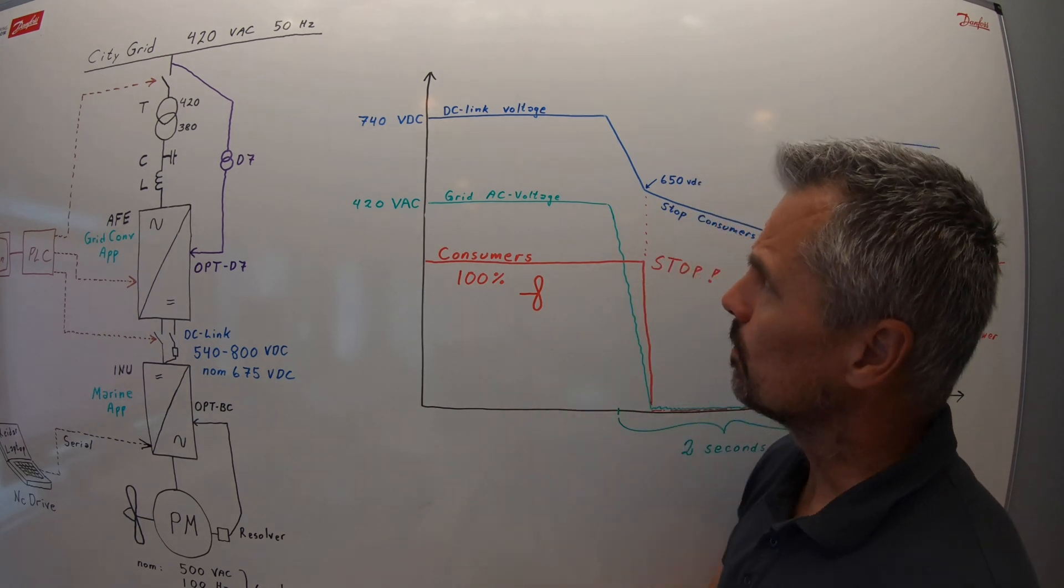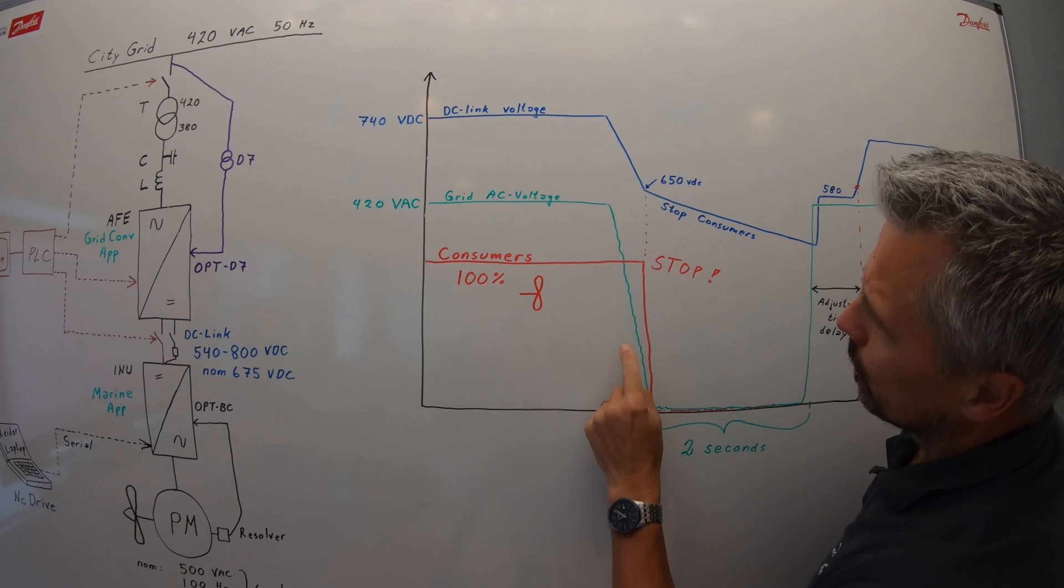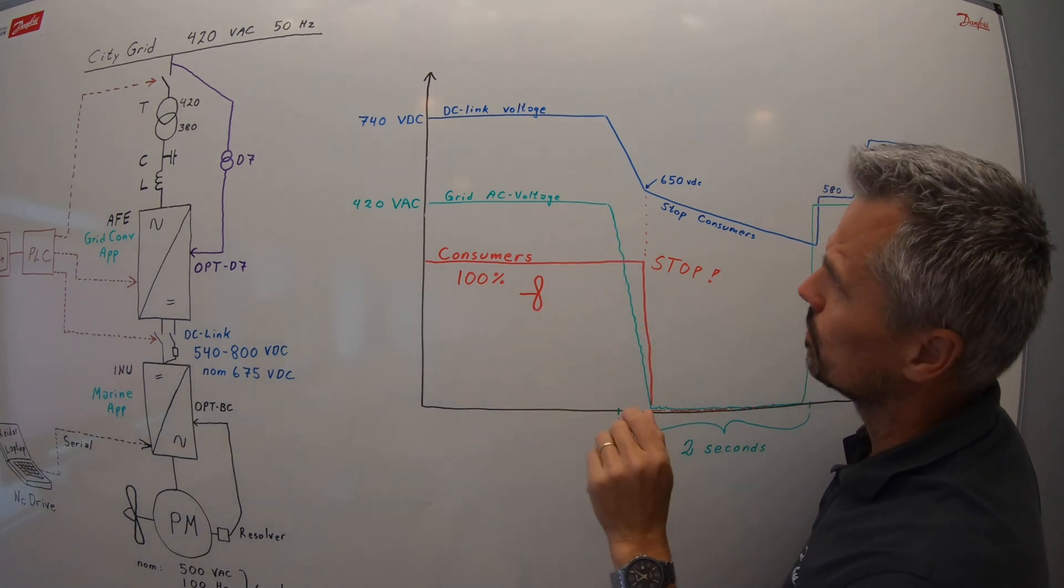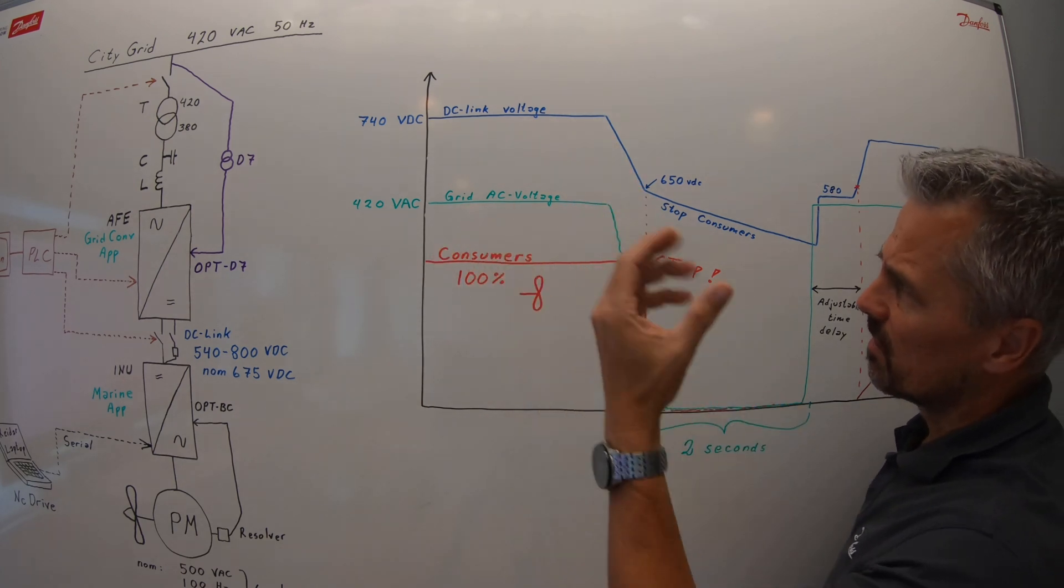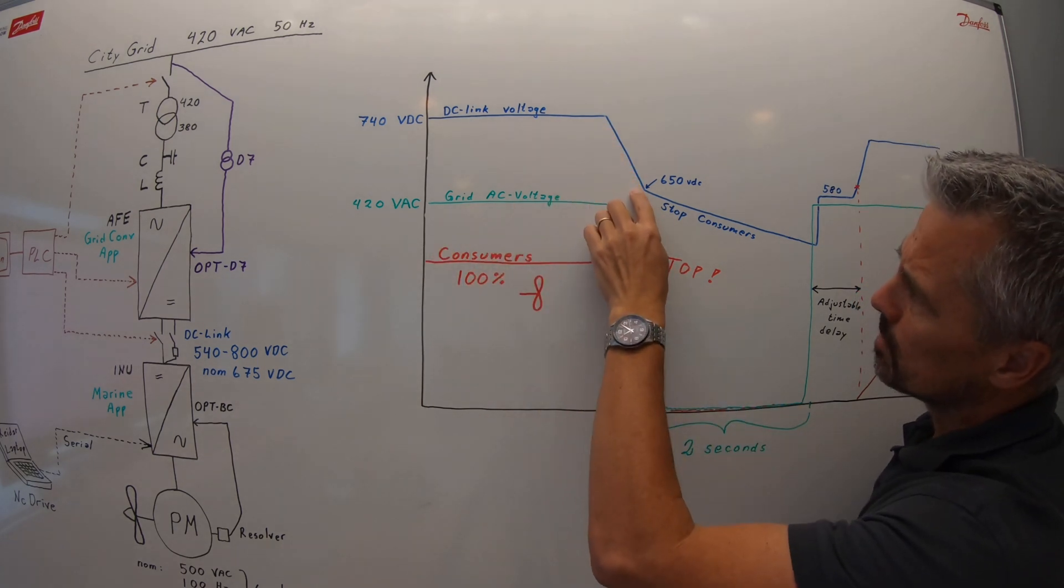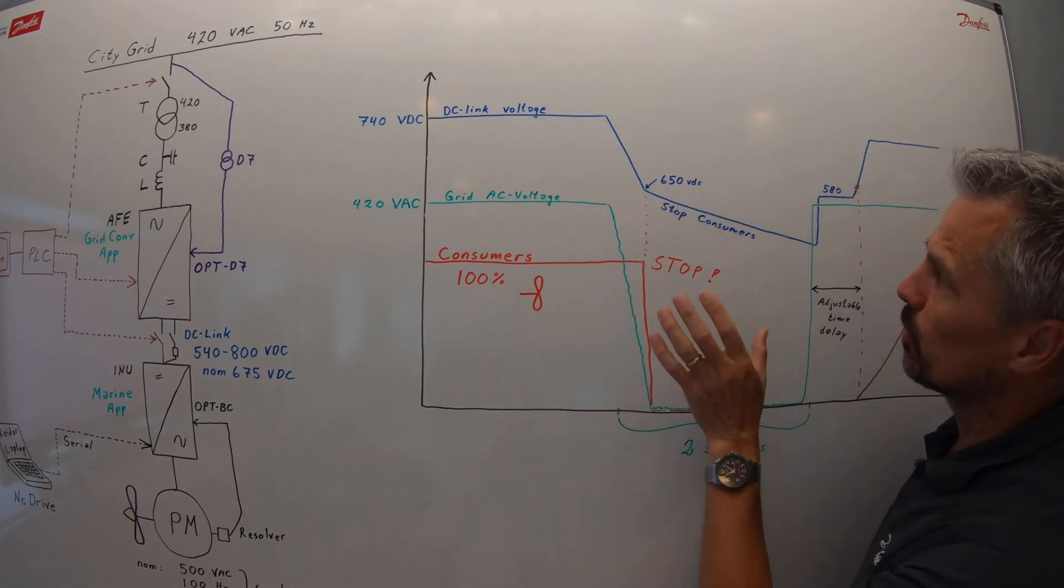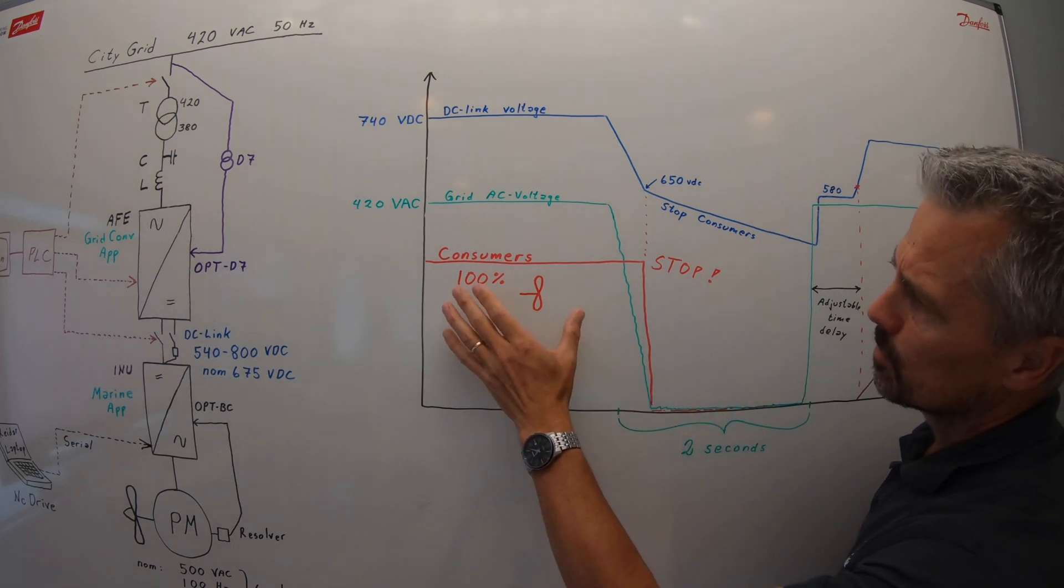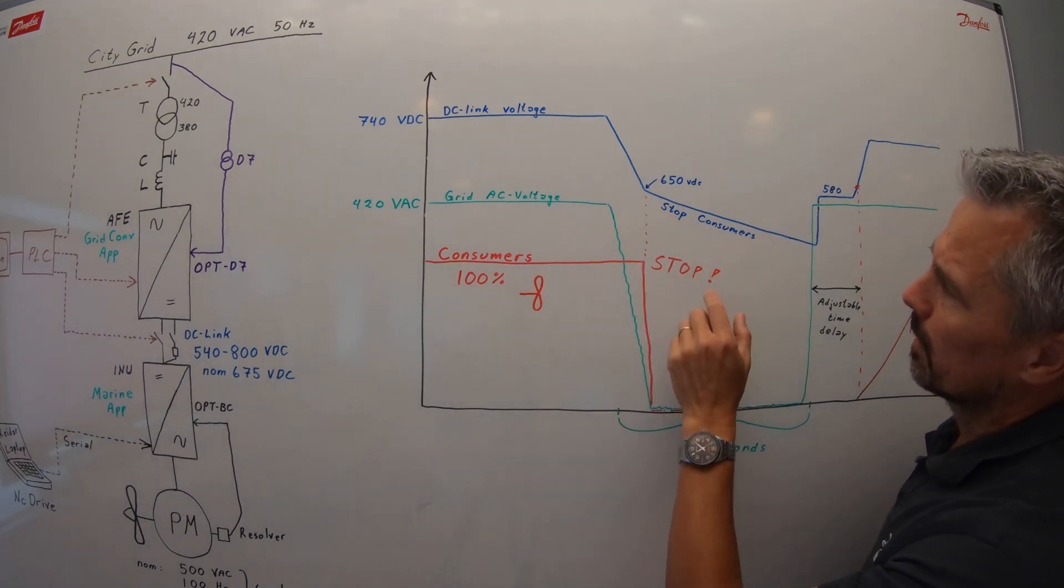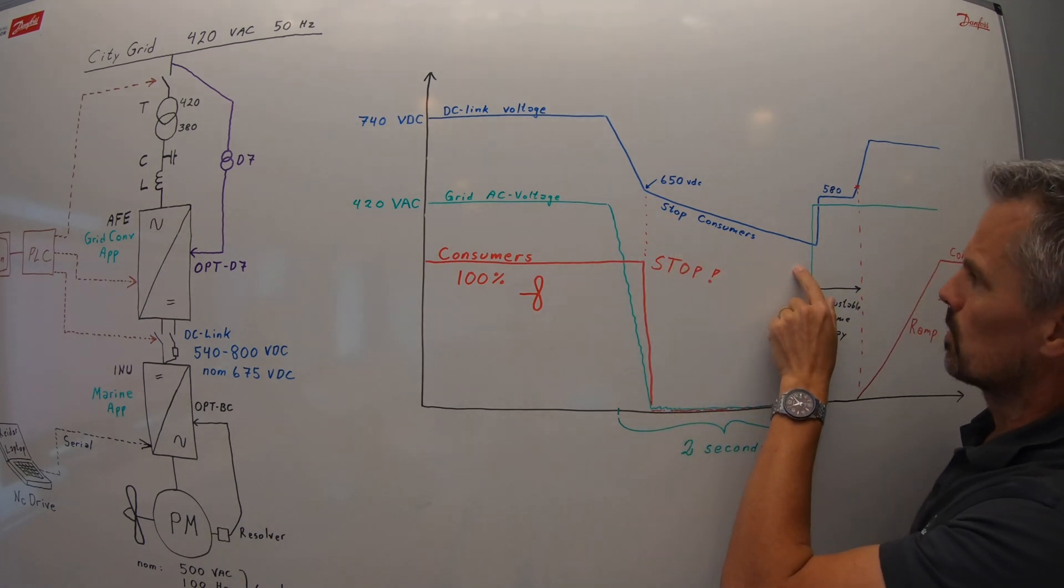On the DC volt, it looks like this. When you have the green curve here, the AC voltage drops, the consumers will extract energy still from the bus down to the level we have set on the inverters, where they stop, stop extracting energy. So the propellers, consumers, they will stop extracting. In this way, we preserve the DC link as long as possible.